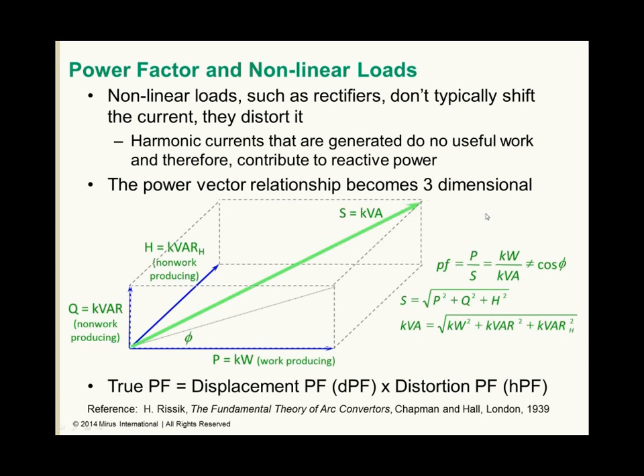So power factor is still real power over apparent power, or kilowatts over kVA, but it no longer equals cos theta. Cos theta now is referred to as displacement power factor. Our apparent power now is the square root of all three components: real power squared, reactive power, that's inductive or capacitive, Q squared, and the harmonic distortion component, H squared. So true power factor now is equal to the displacement power factor, DF, which is equal to cos theta, times the distortion power factor component, or HPF.